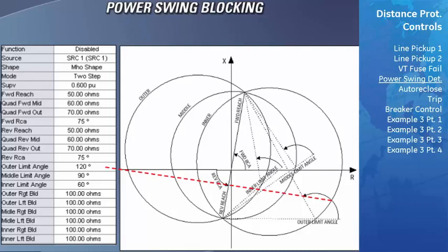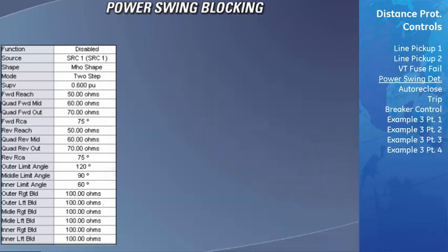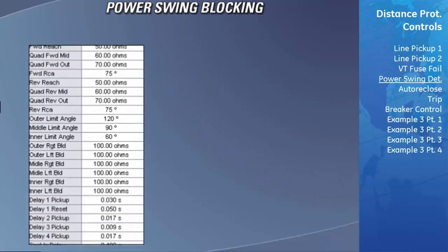Consideration must be taken when setting this angle to make sure the impedance, when under maximum load, will not fall into this region. The power swing middle limit angle is used for setting the shape of the middle zone in a 3-zone blocking characteristic. The power swing inner limit angle defines the shape of the inner power swing detect characteristic. The inner characteristic typically needs to be larger than our Zone 1 characteristic to ensure that power swing blocking will pick up before the impedance locus reaches Zone 1.